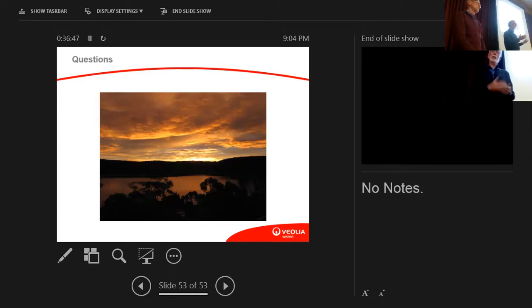Another thing I didn't mention is what happens with the seawater. To produce, say, 50 million litres, we take in 100 million litres, and then another 50 million litres goes back out, with twice as much salt in it. The other 50 million litres goes into the network. So the way it's designed, there are risers in the ocean which come out of the base about 100 metres off the cliffs of Kurnell, and they meet the current going south.